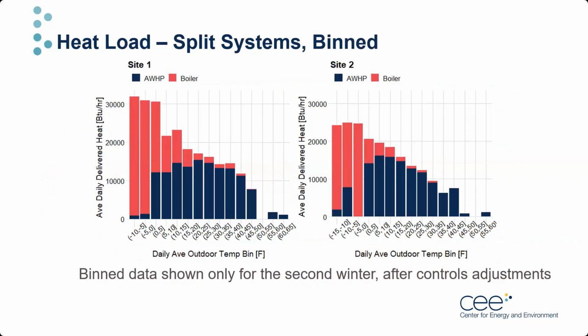Here is the same data from the second winter only, binned by OAT and including only data from after the controls adjustments. We found that these systems perform very similarly to their air-to-air cousins with an auxiliary backup heat source. The key point here is that they are able to displace a majority of the home's heating load through the year.